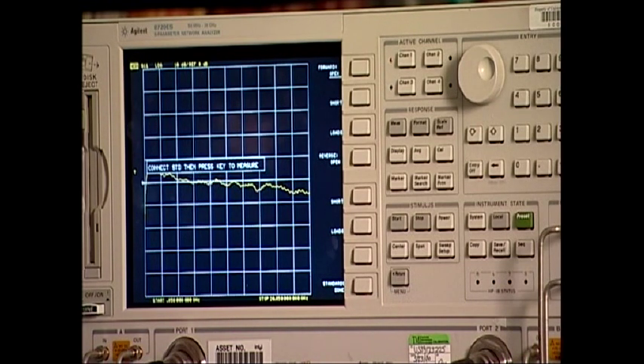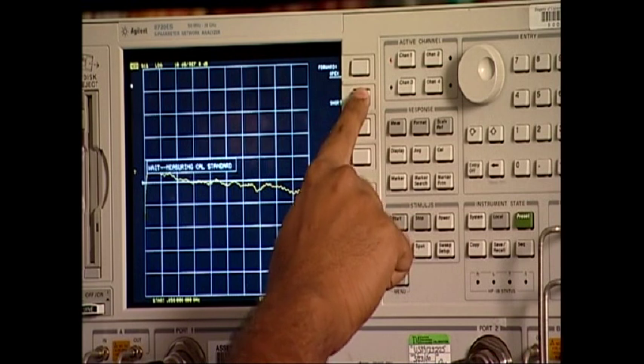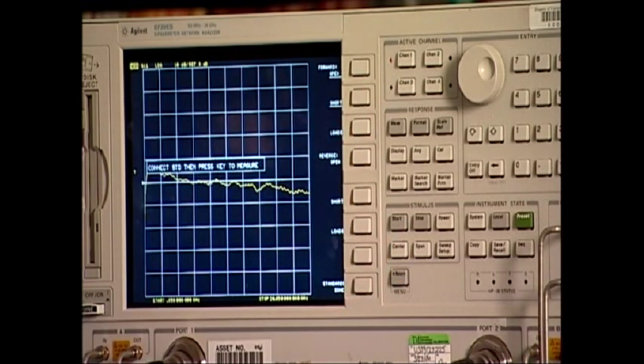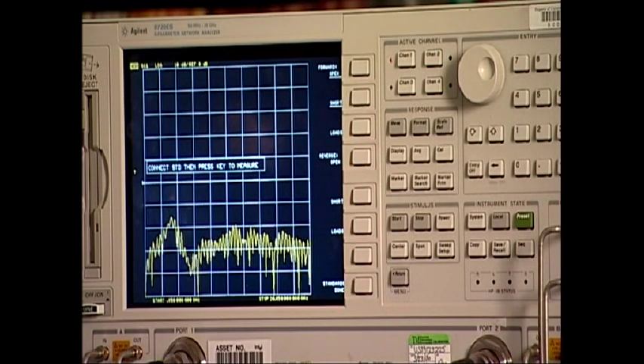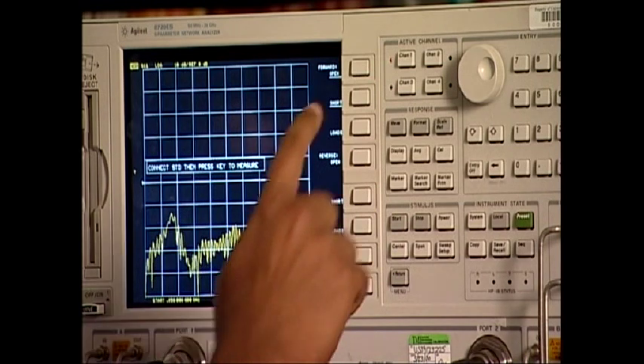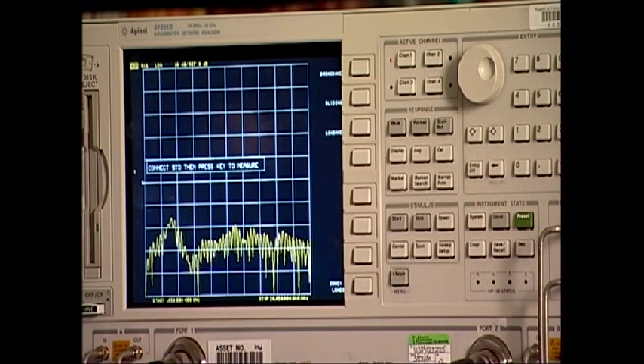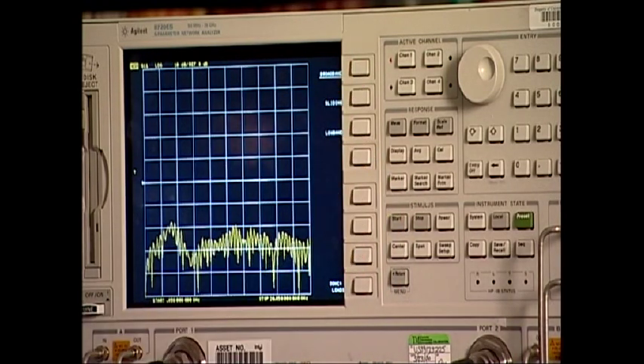Next, we connect the short standard to the cable at port 1 and select short. Next, we connect the load standard to the cable at port 1 and select loads. Now here, since the load we're using is a broadband load, we select broadband. Once this is done, we select done loads.